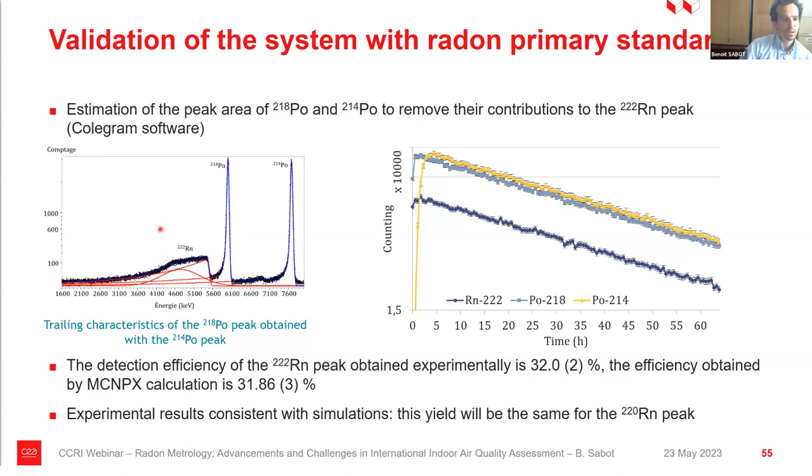But what is important is that this device was developed so that we can directly have radon measurement spectra that is, of course, disturbed by the atoms of air, because it's quite easy to stop alpha in air, but still it has enough shape so that we can discriminate it from the decay products. And here you have the two decay products of radon that were caught on the surface of the silicon detector, and that will then produce very nice thin peaks because they are just on the detector. And so you have very nice peaks with very good resolution.